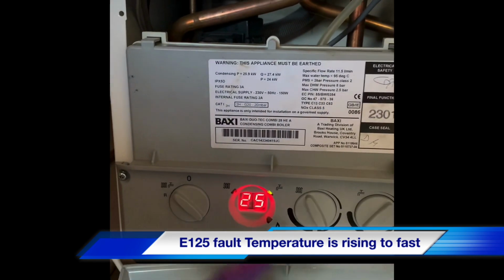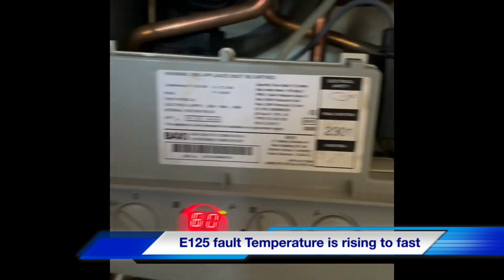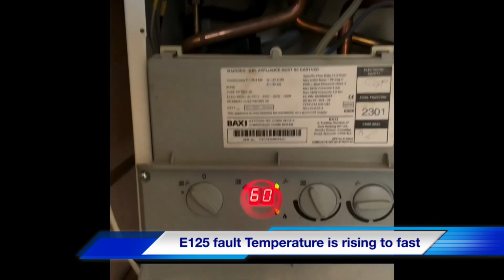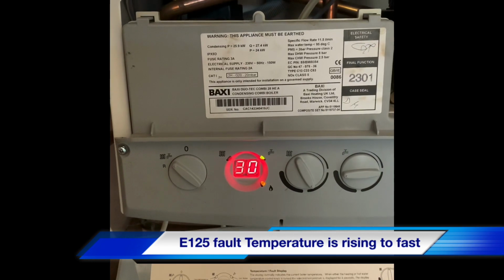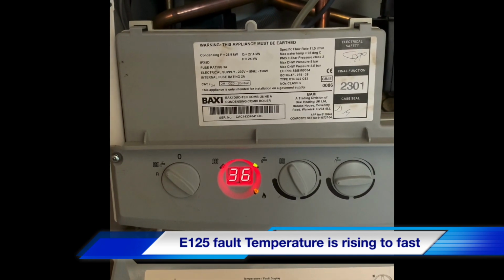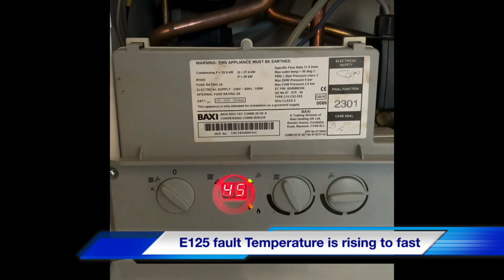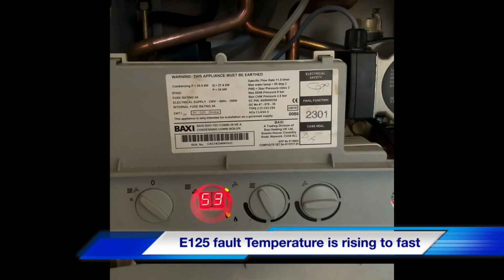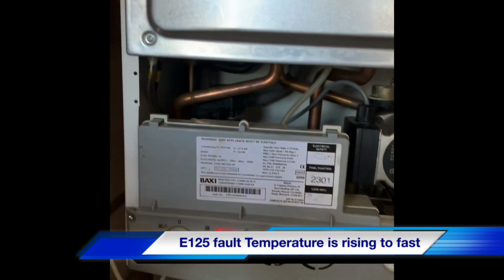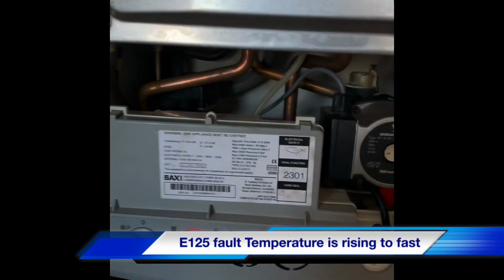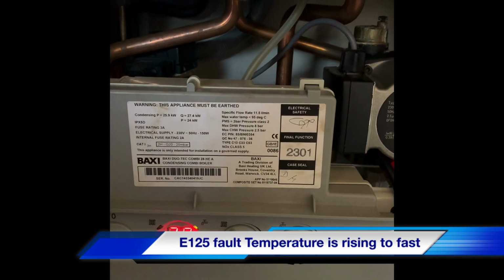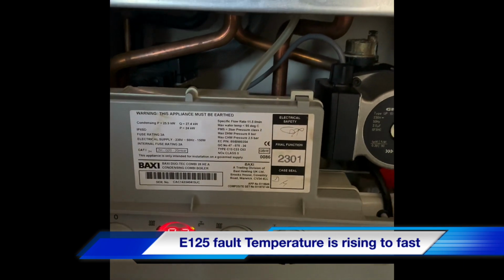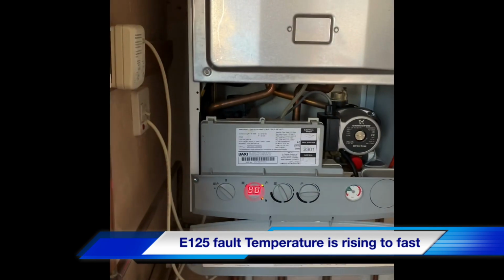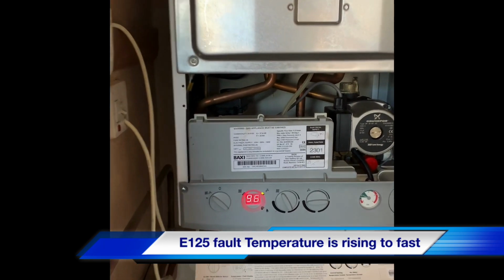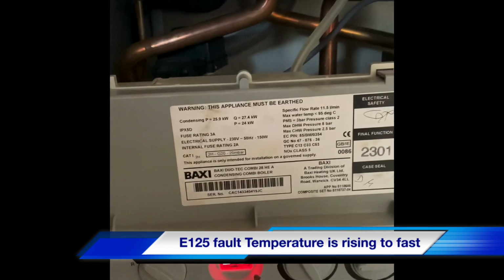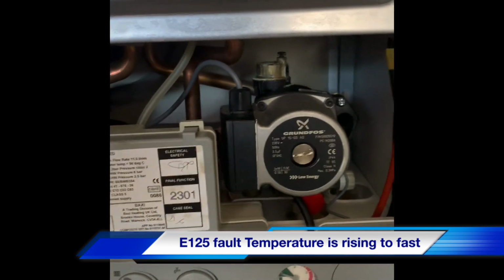So we have demand for hot water. It's now fired. Well, as we can see, temperature is increasing quite dramatically. Very quick, that's going to go to overheat mode. There we go, boiler shut down, it's overheated. So we're going to do some tests on this.